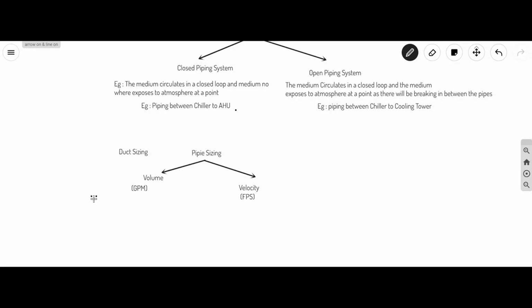So for open piping system, GPM equals TR into 3.0. Standard formula, sir. For closed piping system, GPM equals TR into 2.4. Okay, FPS. Velocity. FPS means feet per second.